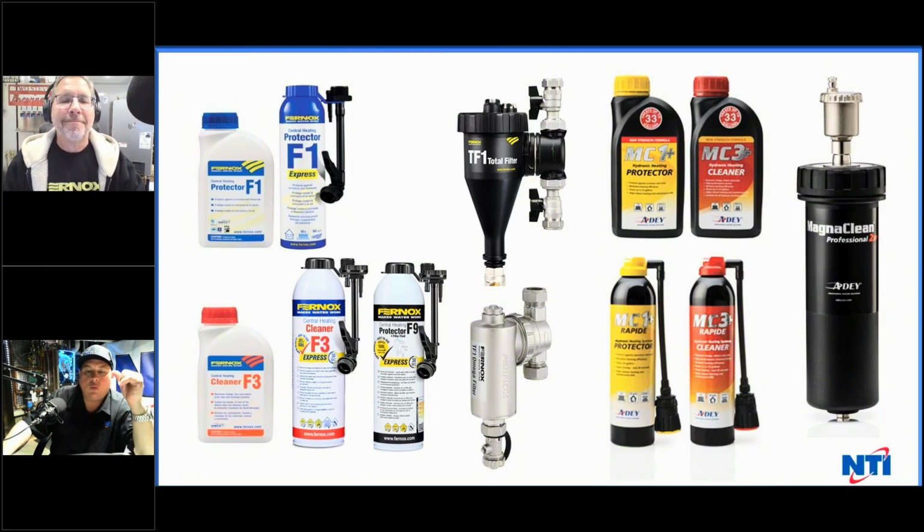Thank you, because I asked that question because I wanted to open up the door. Guys, when you have antifreeze, keep in mind, if it's a special antifreeze, you must use their inhibitor, but test it every couple years because it loses its viscosity and it loses its intensity to inhibit any problems in the system. So I'm telling you, check it. It's an issue. Guys, remember, it traps air, so when you use it in large content, it creates issues.